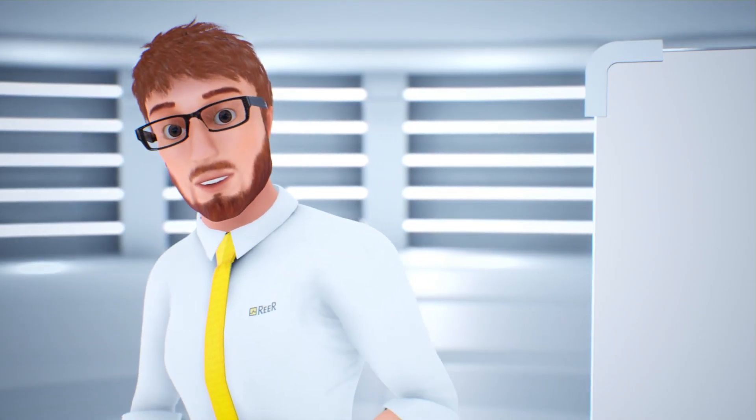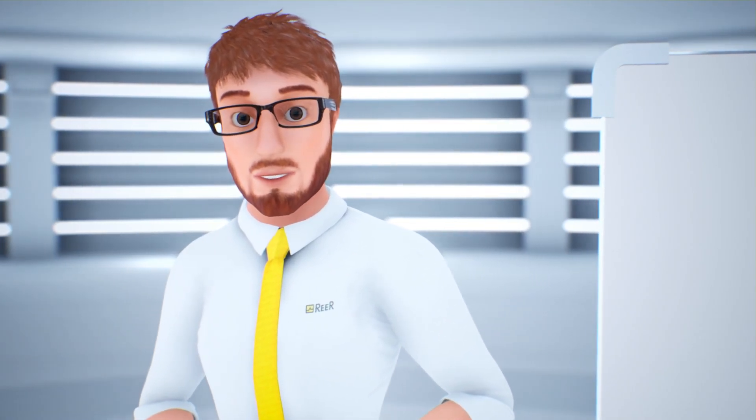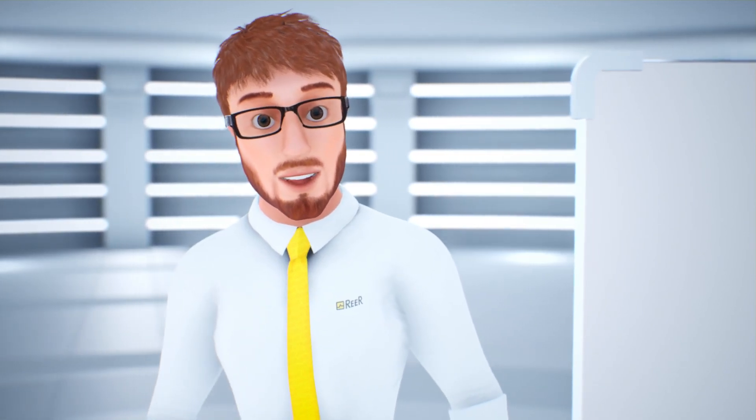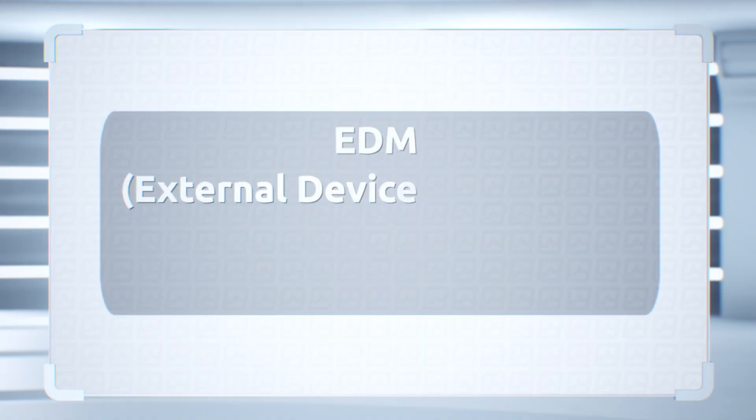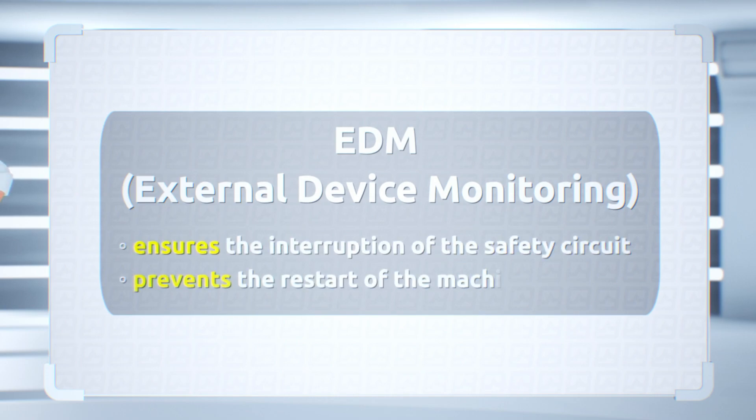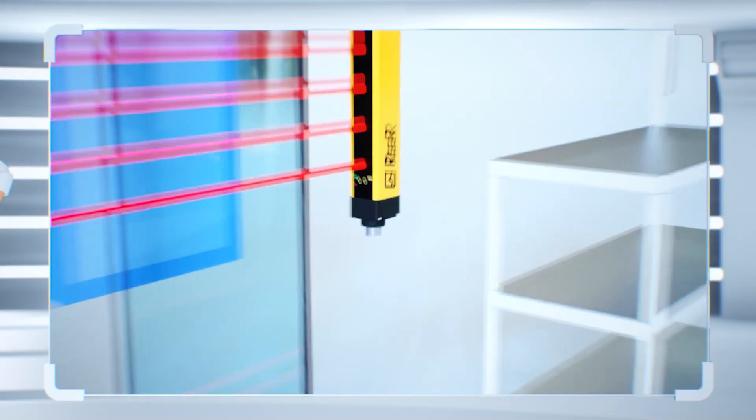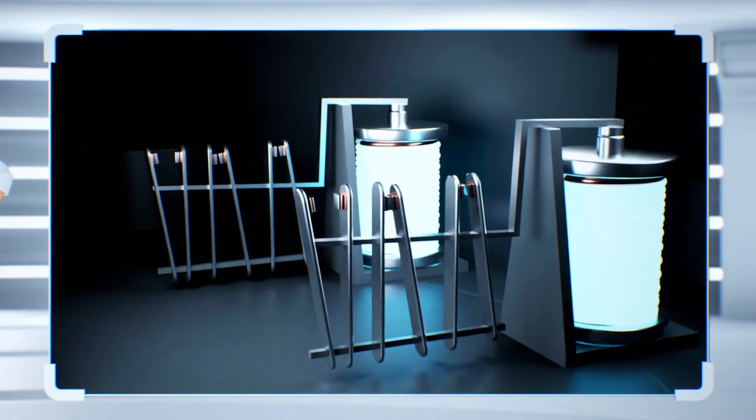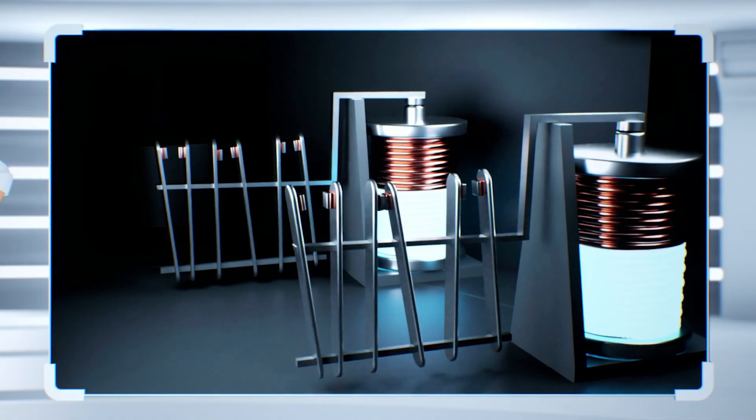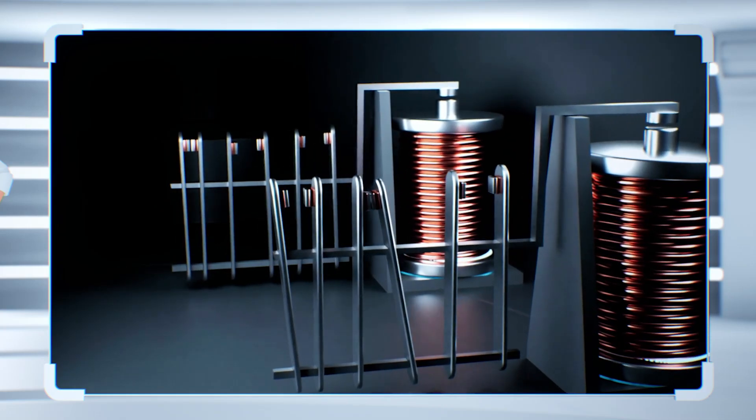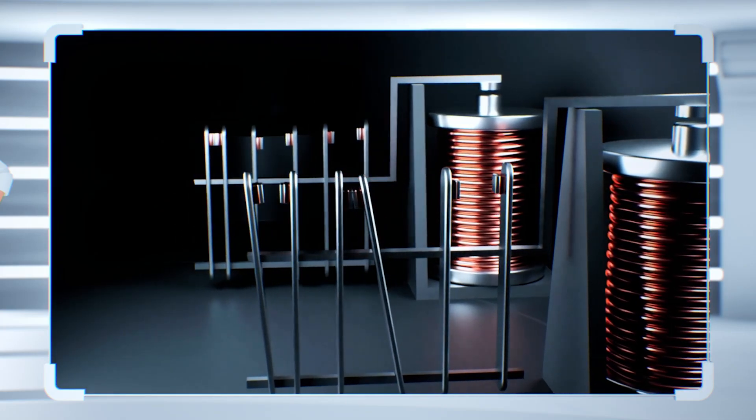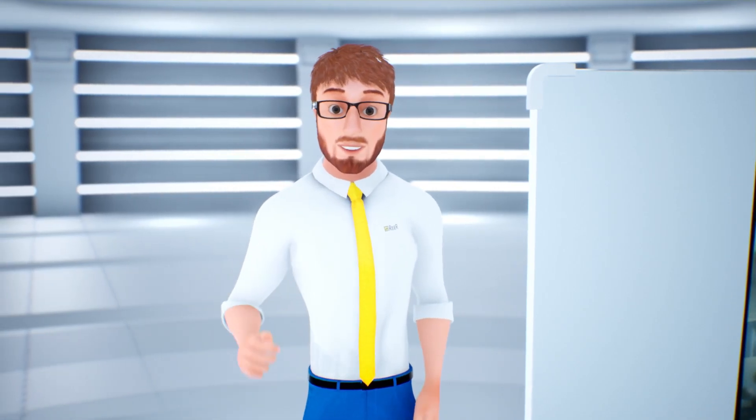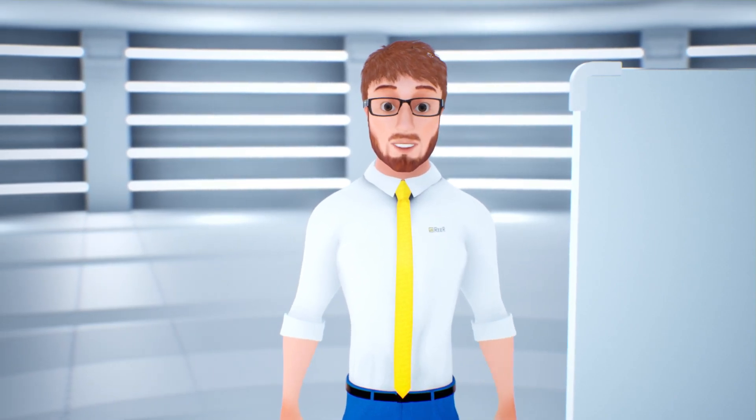It ensures that the external device connected to the safety device, for example a safety light curtain, can interrupt the safety circuit and eventually stop the machine. The safety relays provide feedback through the normally closed auxiliary contacts, connected in series and forcibly guided by its normally open safety contacts. When a fault is detected, this circuit prevents the reset of the safety device and, therefore, the restart of the machine. Do you feel that you now understand how this process works?